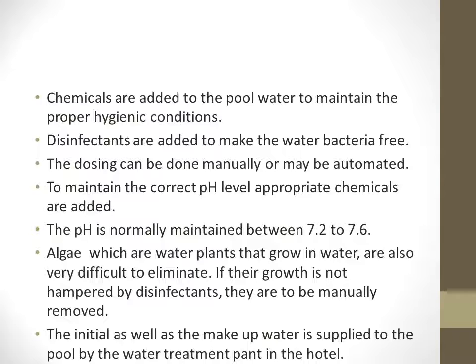To maintain proper hygienic conditions, we use chemicals such as chlorine. We also add disinfectants and other factors so that the water will be bacteria-free. Disinfectants can be added automatically or manually. We also need to maintain and take care of the pH value — the standard range is 7.2 to 7.6.